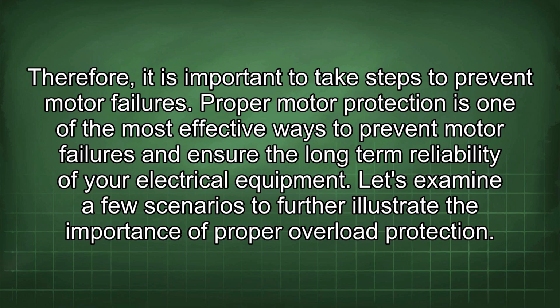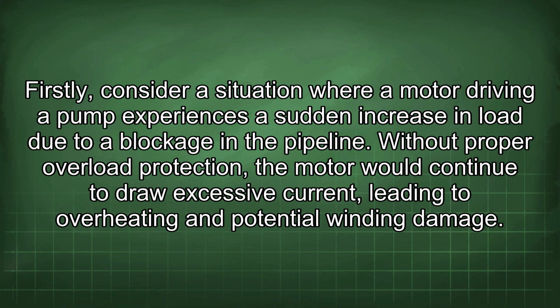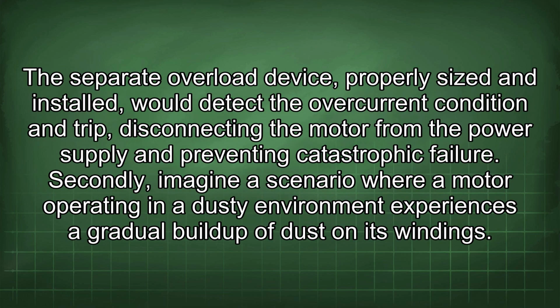Let's examine a few scenarios to further illustrate the importance of proper overload protection. Firstly, consider a situation where a motor driving a pump experiences a sudden increase in load due to a blockage in the pipeline. Without proper overload protection, the motor would continue to draw excessive current, leading to overheating and potential winding damage. The separate overload device, properly sized and installed, would detect the overcurrent condition and trip, disconnecting the motor from the power supply and preventing catastrophic failure.